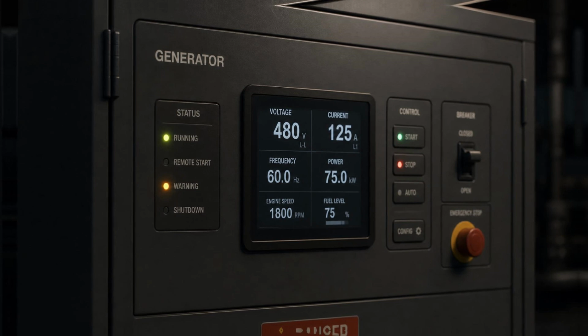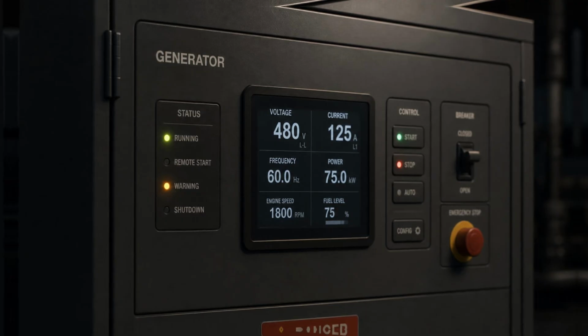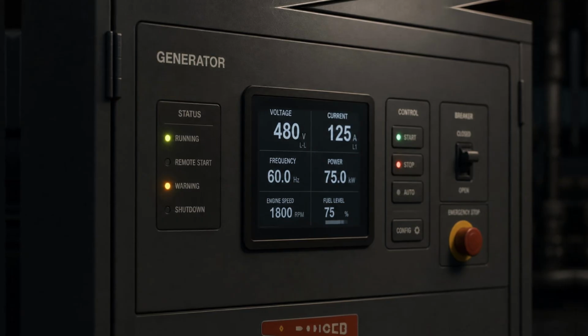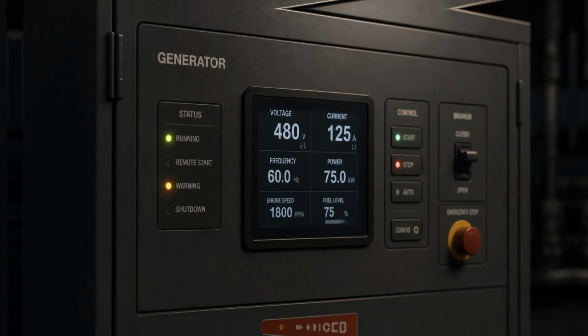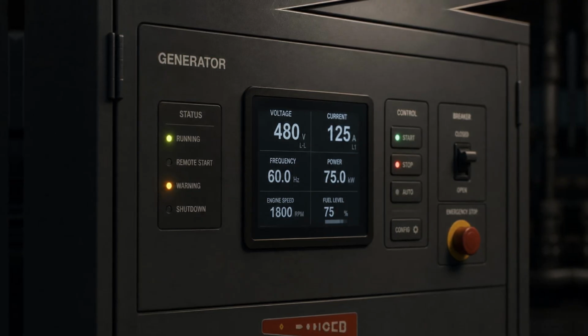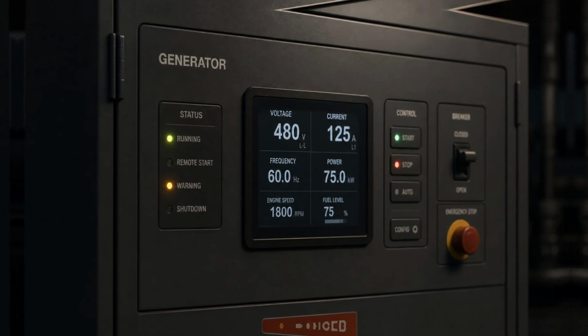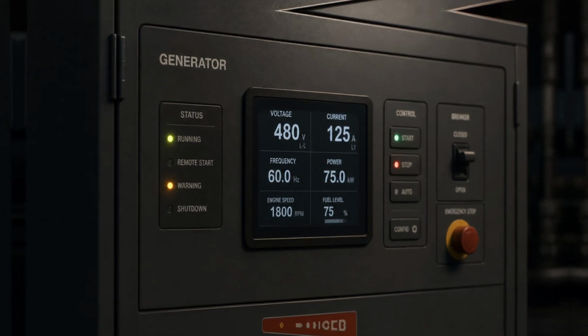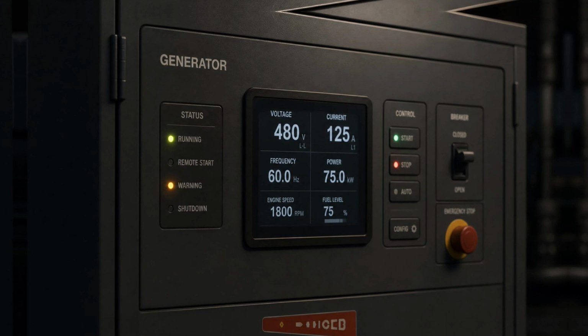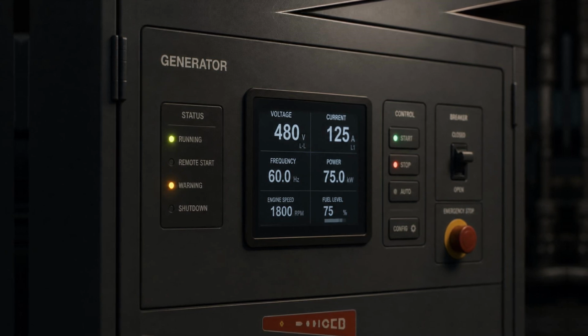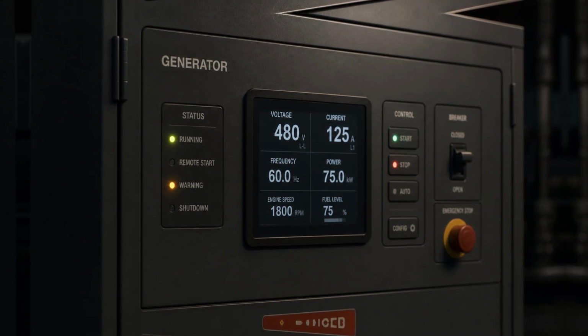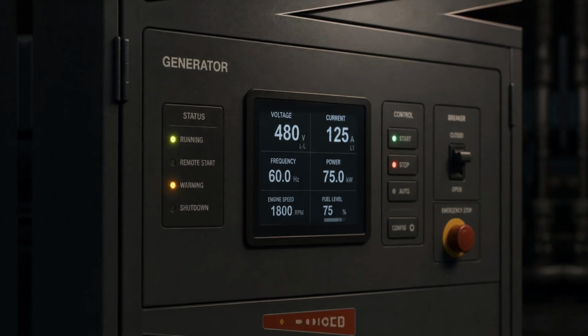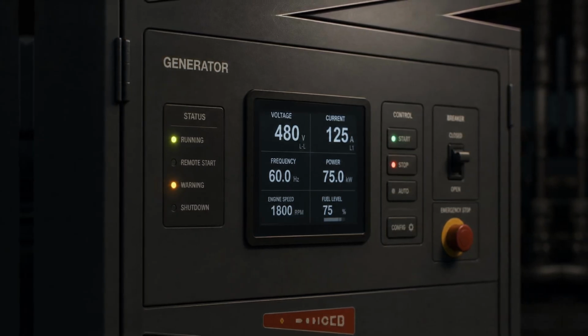The sizing is deliberate, chosen to match the expected generator start time with a margin for safety and for the unexpected. When the generator comes online and the transfer switch delivers generator power back to the UPS's input, the rectifier begins charging the batteries again. The gap has been crossed, the load has been held through the transition, and the UPS settles back into its normal operating state. Inverter running, batteries charging, the downstream equipment entirely unaware of what just happened.